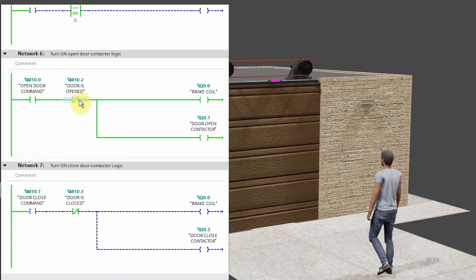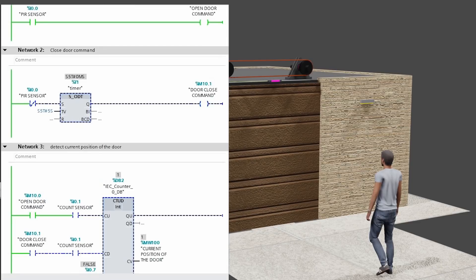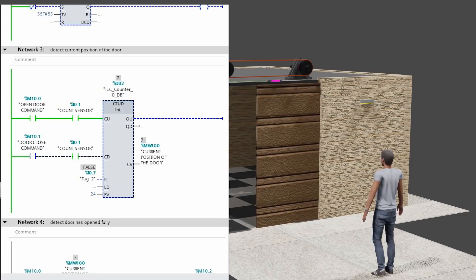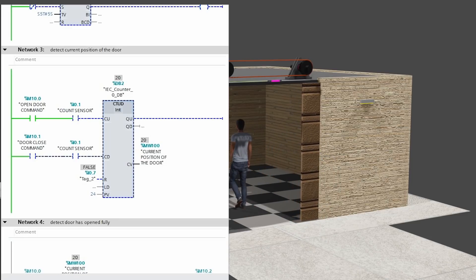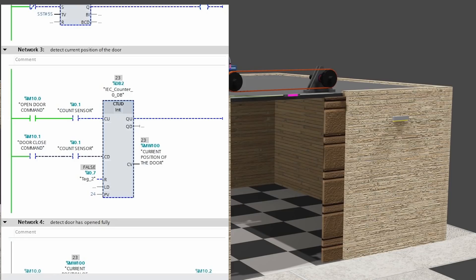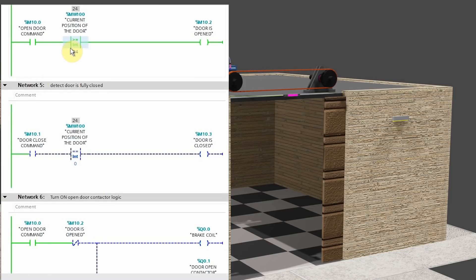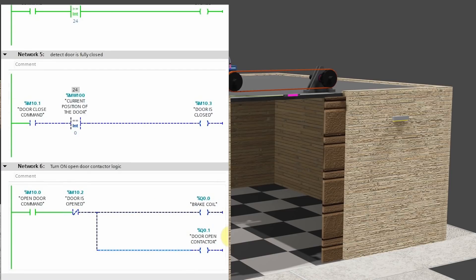In Network 6, the brake coil and door open contactor are turned on and the door starts to open. Looking at the counter, the current value is incremented by one with each pulse from the count sensor, so we are tracking the current position of the door. As soon as the current counter value reaches 24, the door stops moving. The comparison operation turns on door open bit M10.2 and the normally closed contact of M10.2 opens up, turning off the brake coil and the door open contactor.